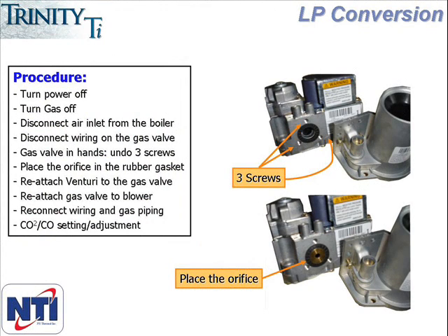If you are converting a boiler to LP for a new installation, it's best to do it before it's been hung on the wall. The three screws that need to be removed are located on the bottom of the gas valve, so it's a little easier to get at them before it goes on the wall. When converting a unit that's already been installed, make sure the power and gas are turned off and disconnect the air inlet from the boiler.